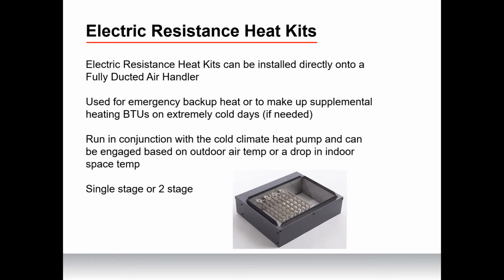So electric resistance heat kits can be installed directly onto a fully ducted air handler, used for emergency backup heat or to make up supplemental heating BTUs on extremely cold days, if needed, right? Climate, where are you at? What's your design temp? Those are the things that we're going to need to look at. They run in conjunction with the cold climate heat pump and can be engaged based on outdoor air temp or a drop in indoor space temp.